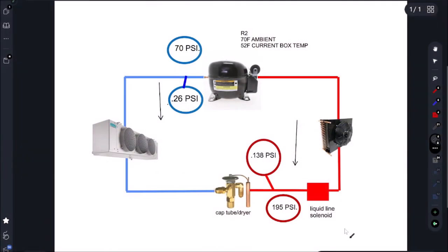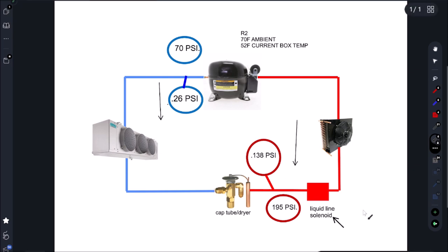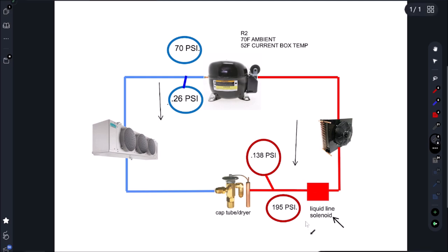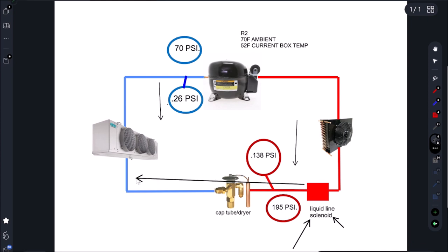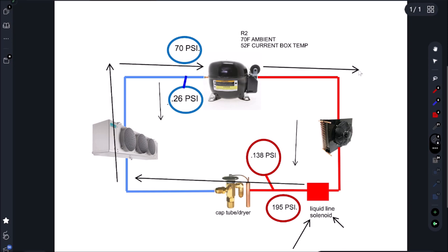Alright, so we need to replace our liquid line solenoid. Why I'm saying that's going to be an issue is because I want to save the refrigerant. So I could potentially recover the refrigerant, but there's a way to park the refrigerant in the system so that we can do a repair on the low side. So I went over this in one of my previous videos, probably three or four videos ago. But the issue with parking it is we're still going to have refrigerant right here at the liquid line solenoid. So let's just go over how the liquid line solenoid works. So this valve will close, the refrigerant will pump this way, this way, and to here, and then we're obviously going to come through this way. We're going to park ourselves in the receiver.